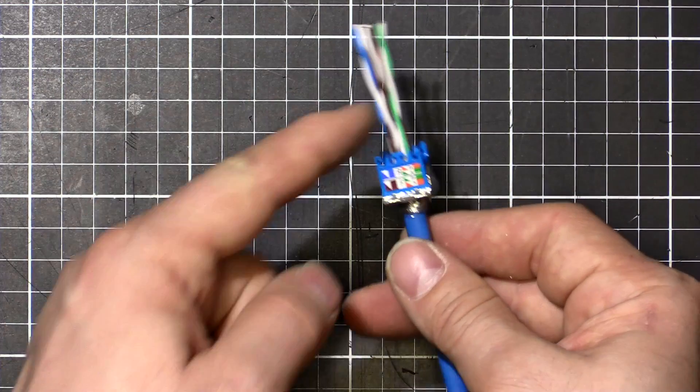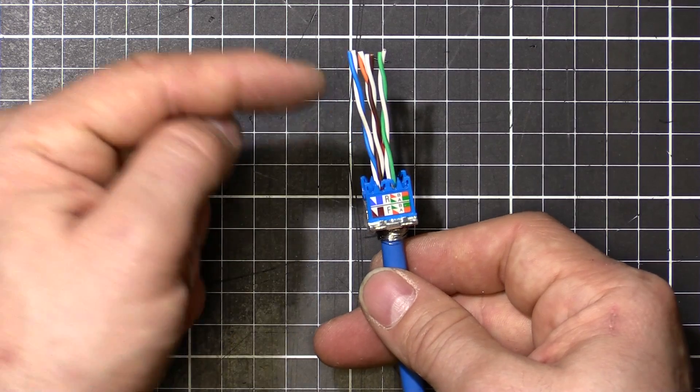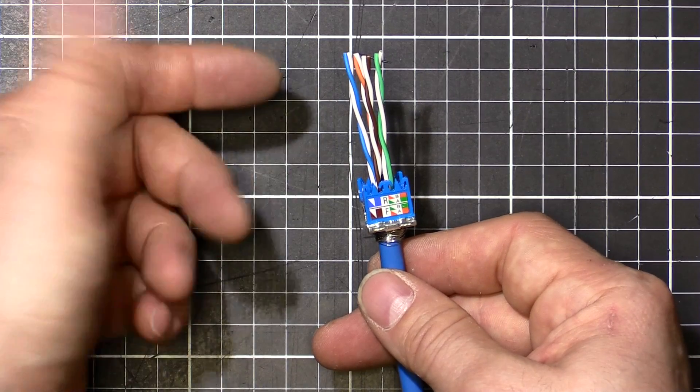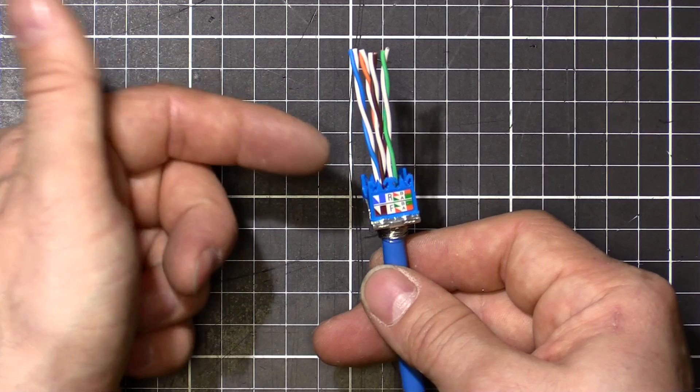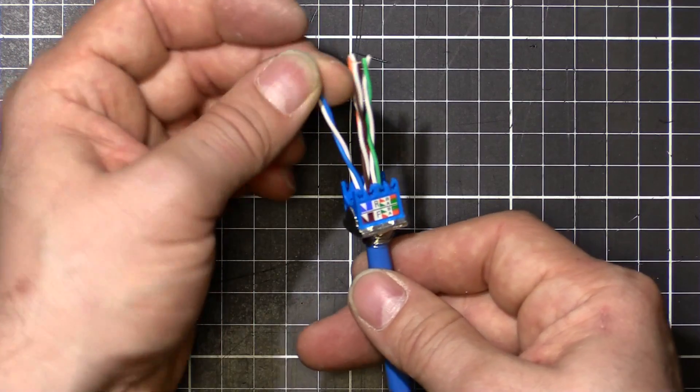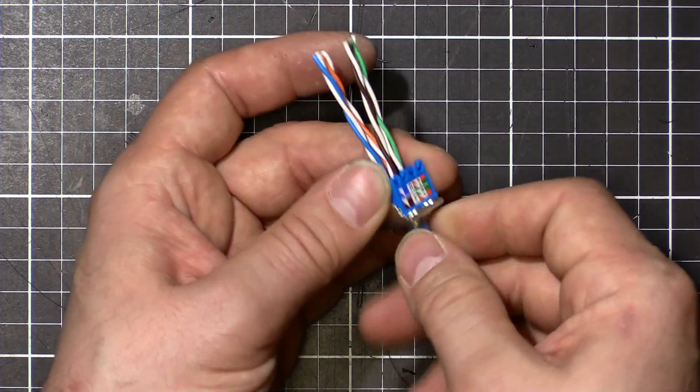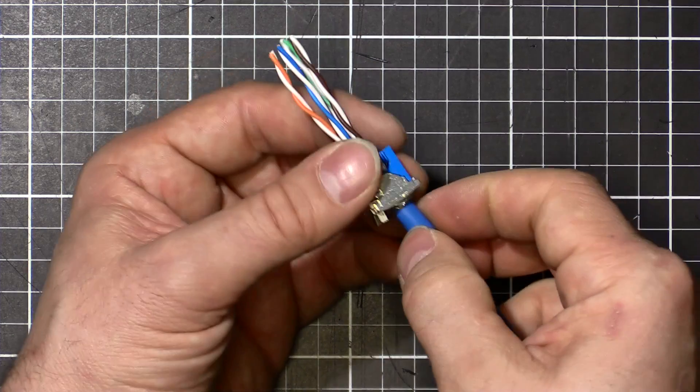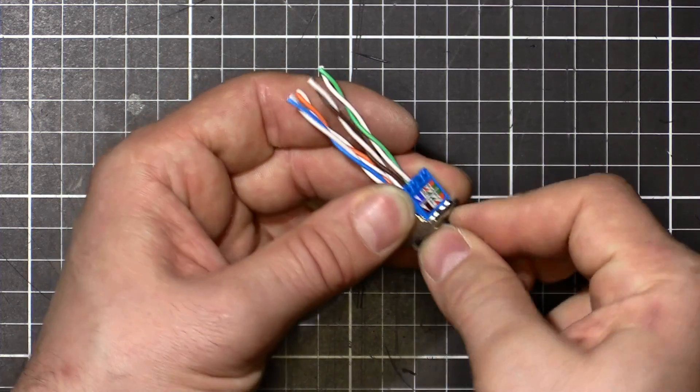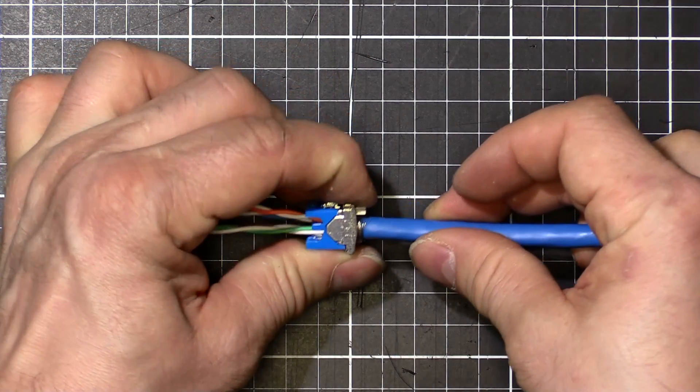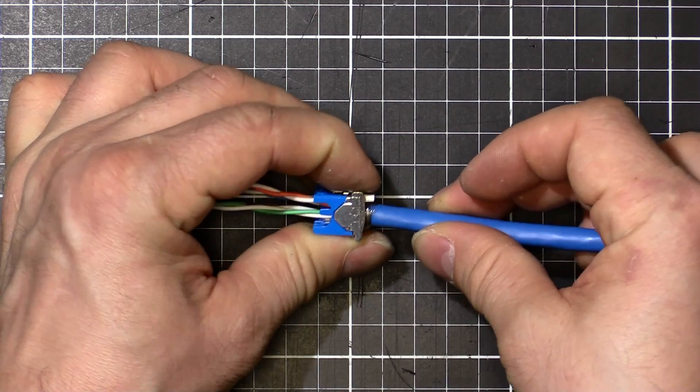Sometimes it can be a bit of a pain. I found that the twist rate on shielded cable is slightly less than on unshielded cable because it doesn't need to be twisted so tightly being shielded. So the conductors can kind of fray just a little bit and they get caught. But this went in not so bad. Make sure we've got it nice and seated there with our shield. And now we can push this piece here down, the locking tab. But it's going to be hard to do that by hand.